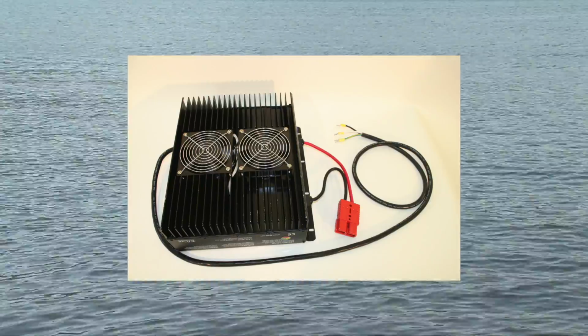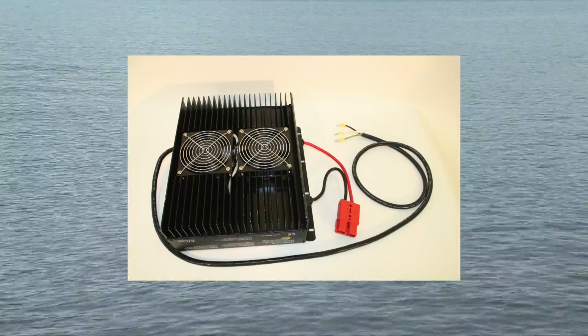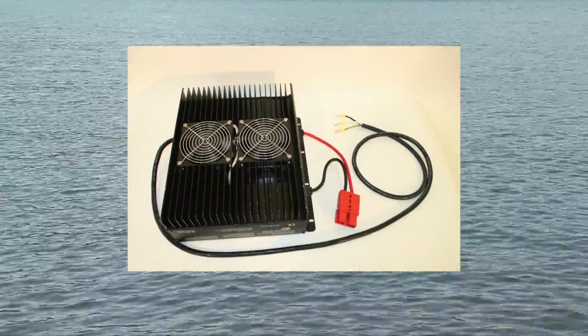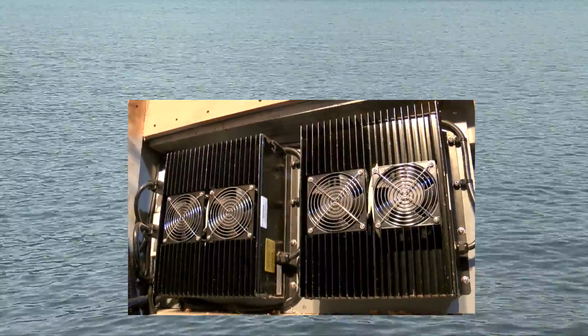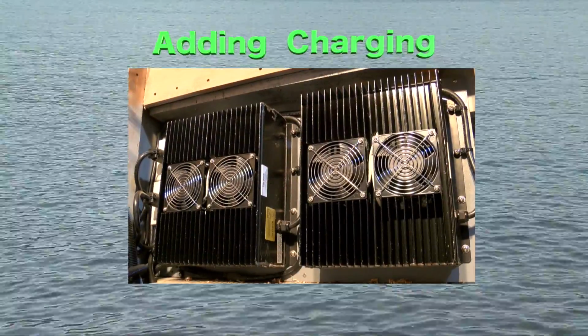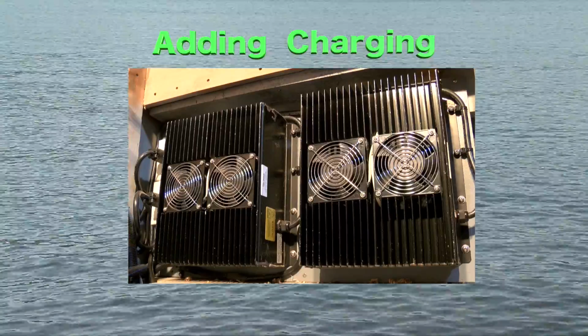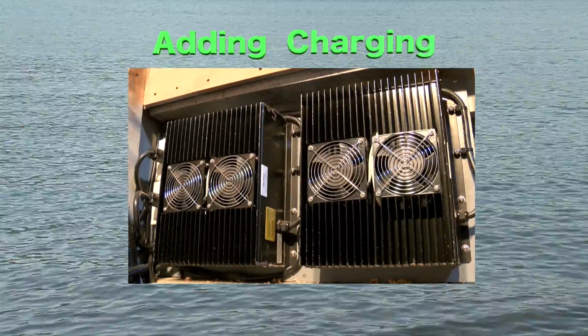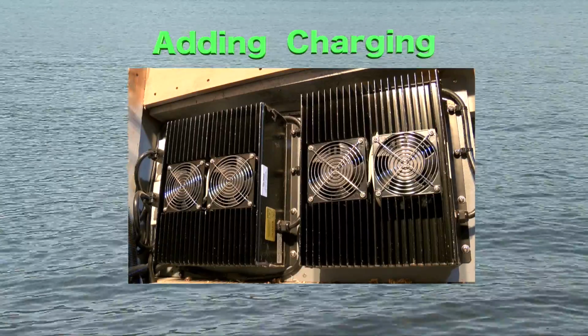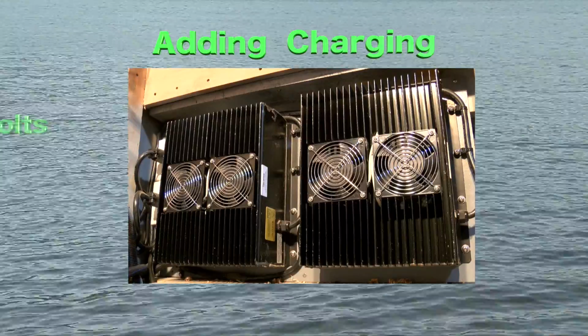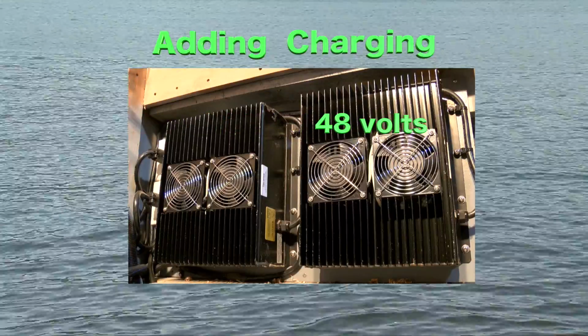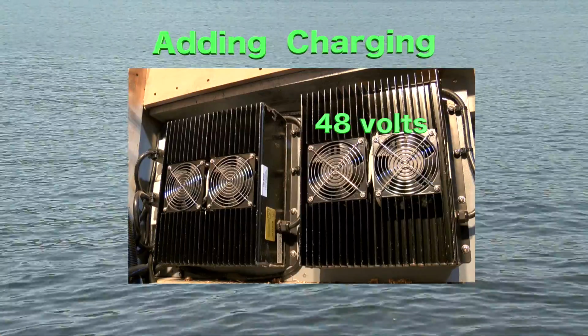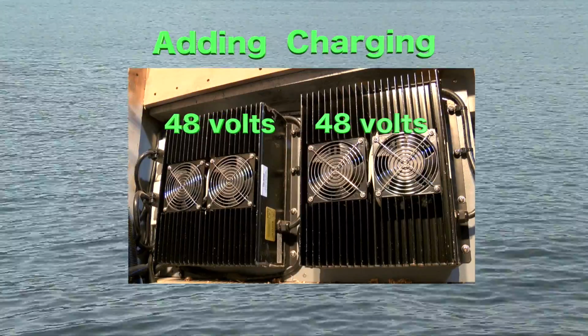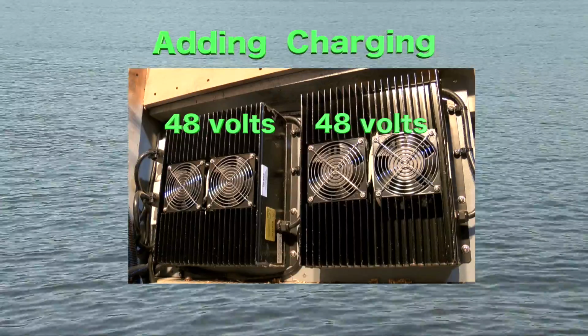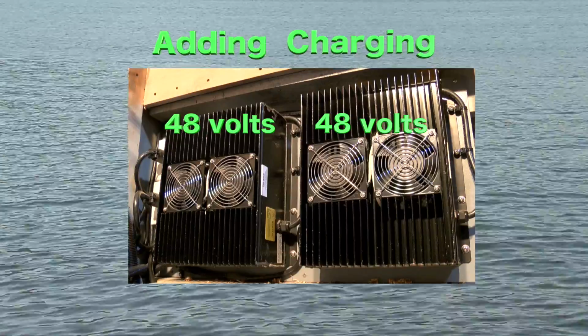If you are purchasing a charger from another source, be certain the charger uses the correct algorithm for your batteries. Additional battery strings may require installing a higher output charger or a second charger. Chargers must be matched in output voltage to the battery system installed. For example, a 48-volt battery bank will require a 48-volt charger.